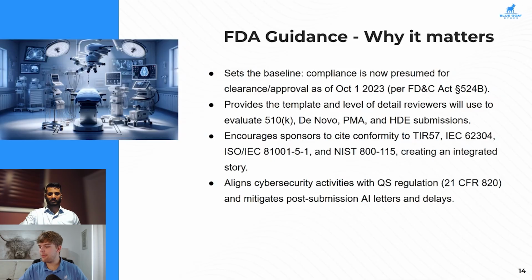Now, we can jump into some of the most recent changes, which has been the buzz on everyone's mind lately. I know that previously, a complaint that just about everyone's had with this FDA approval process is clarity around some of these items. And so the FDA recently just pushed out Section 7 of this guidance document talking about quality considerations for cybersecurity in medical devices. And what Section 7 is doing is they're clearing up the definitions on what is a cyber device. What are some examples of a cyber device? When is this documentation going to be required? When should a resubmission be required?